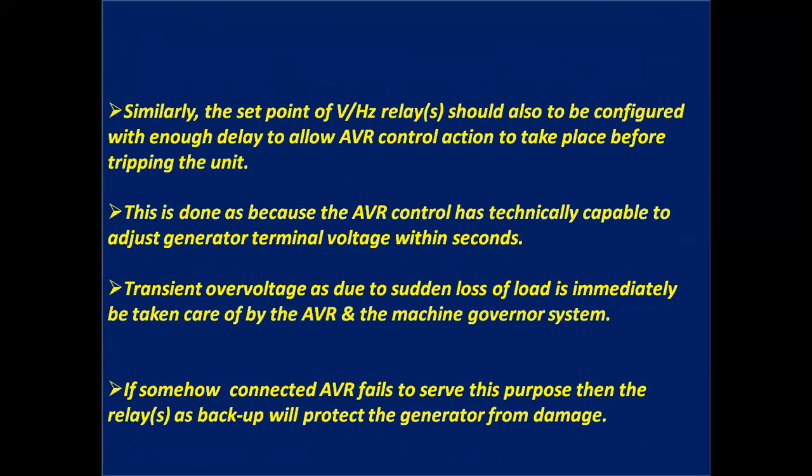Similarly, the set point of volts Hertz relay should also be configured with enough delay to allow AVR control action to take place before tripping the unit.